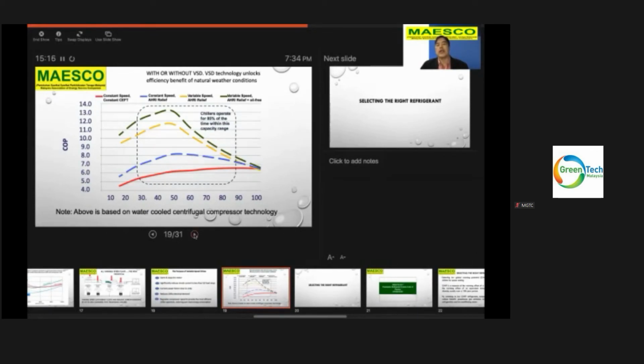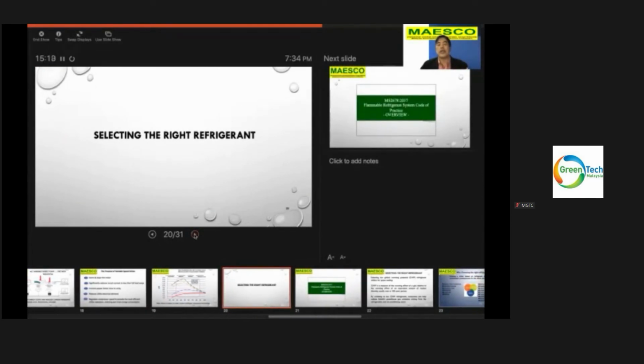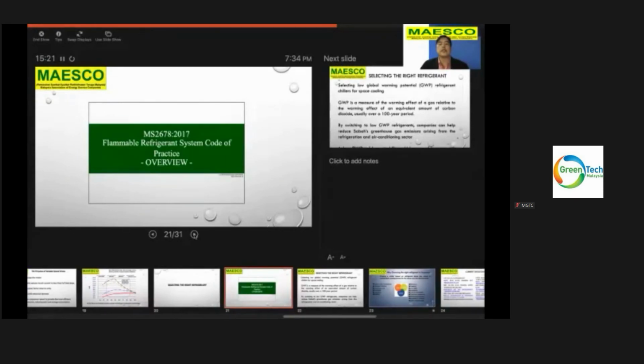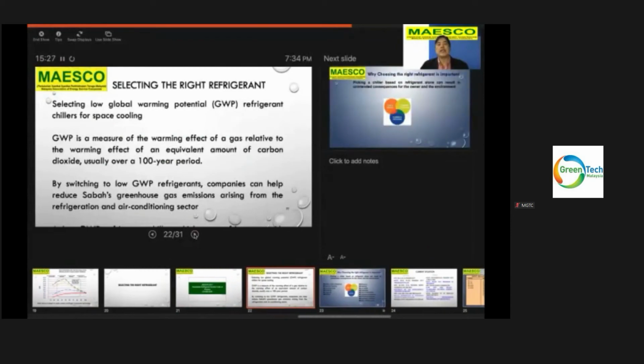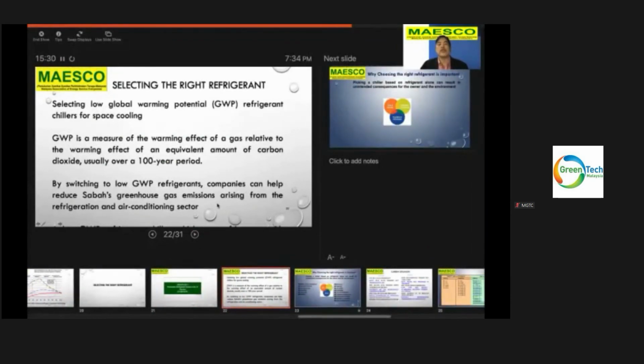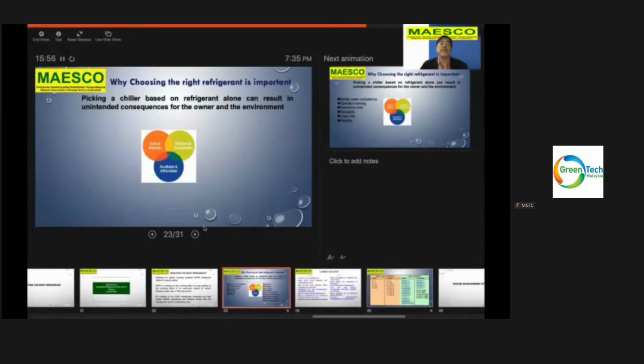Now, secondly, you must select the right refrigerant. These are pretty important. Malaysian standard MS 2678:2017, Flammable Refrigerant System Code of Practice, states selecting low global warming potential refrigerant chillers for space cooling. GWP is a measure of the warming effect of a gas relative to the warming effect of the equivalent amount of carbon dioxide, usually over a 100-year period. By switching to low GWP refrigerants, companies can help reduce our greenhouse gas emission arising from the refrigeration and air conditioning sector. Now, why choosing the right refrigerant is important.